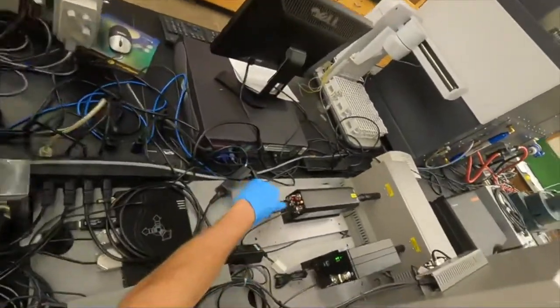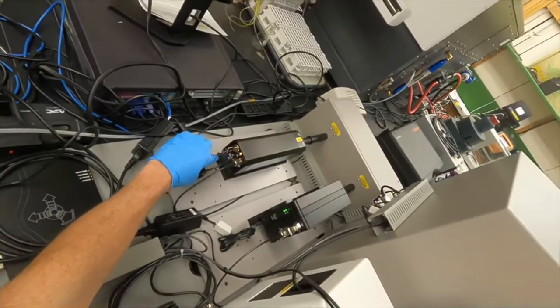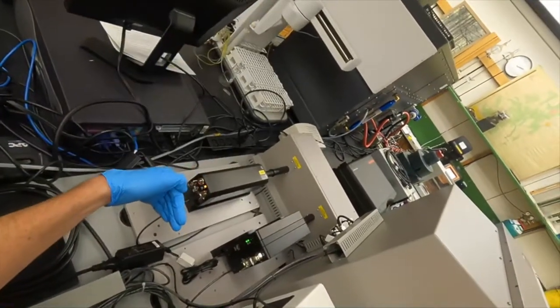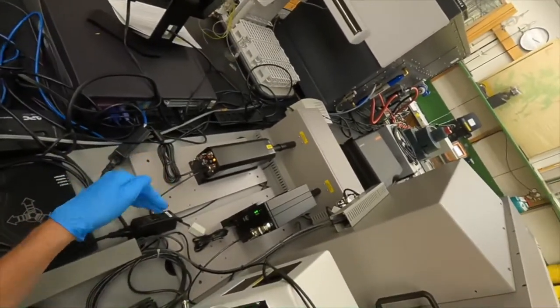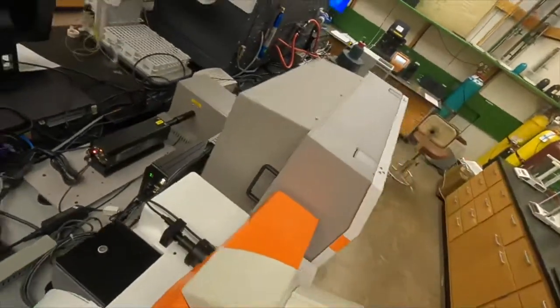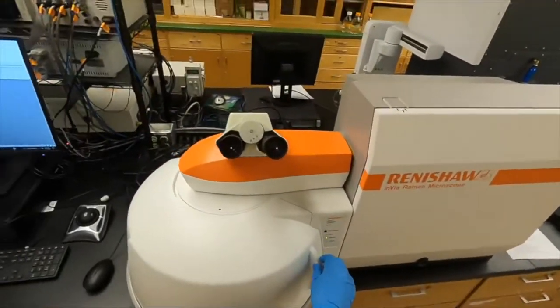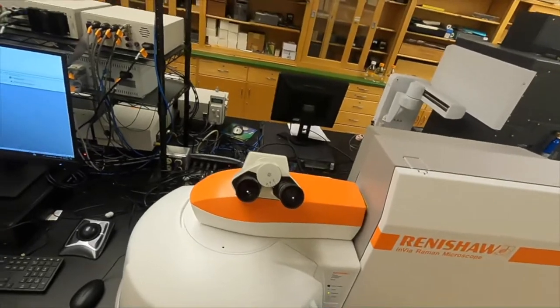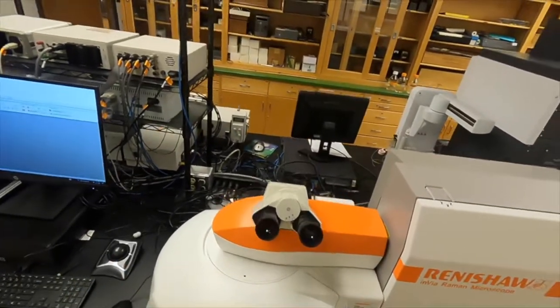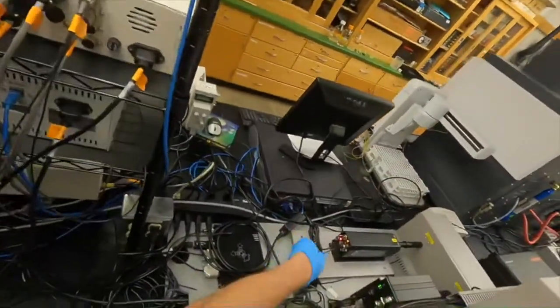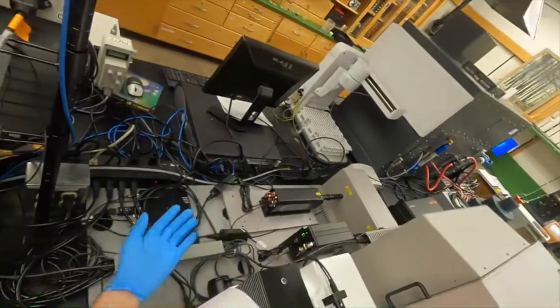Sometimes the bottom two lights will be on, and that means there's a shutter that's closed, blocking the laser from hitting the samples, and that'll cause it to not give good readings. Usually that's triggered by this door. There's a sensor that detects whether the door is open or not, to protect the laser from coming out and hitting you in the eyes. So if the top light doesn't come on, it's not going to give you good readings.